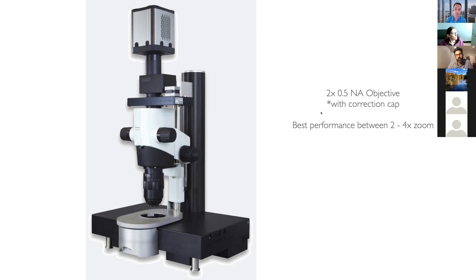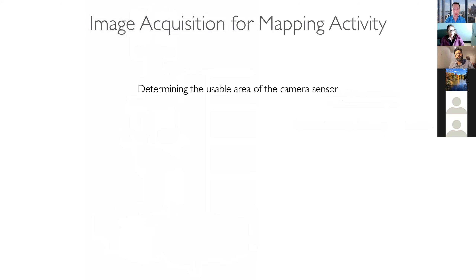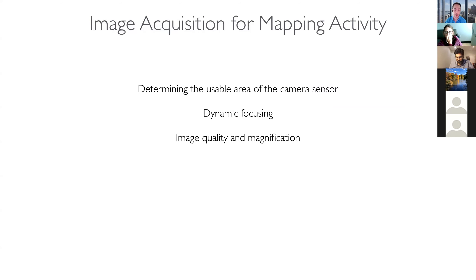At the Zuckerman Institute we have one of these UltraMicroscope II light sheet microscopes, used by a lot of the whole-brain imaging groups — the same type used in the Cell paper. We have a 2x objective with a correction cap, which gives very little distortion and works best between 2x and 4x zoom. Before getting into the ClearMap pipeline, I want to briefly touch on how to get a good image for mapping: how much of the camera sensor to use, whether to use dynamic focusing, image quality considerations, magnification, and how to save time during acquisitions.